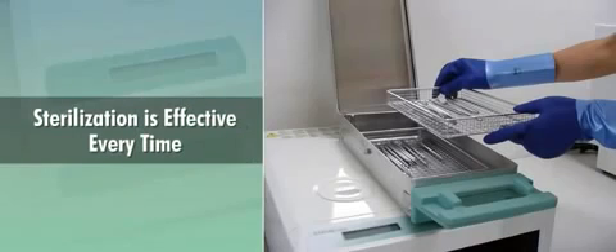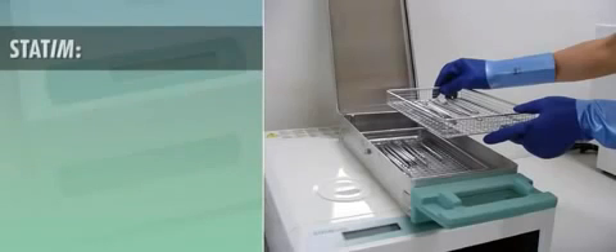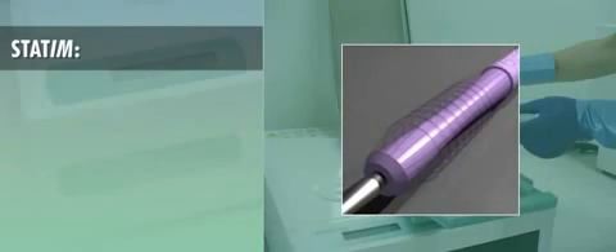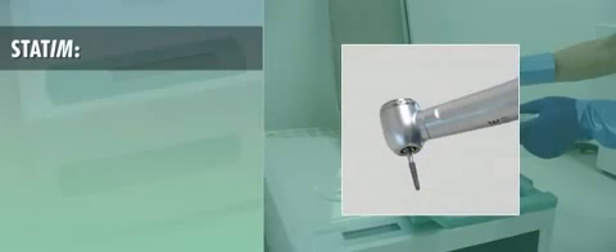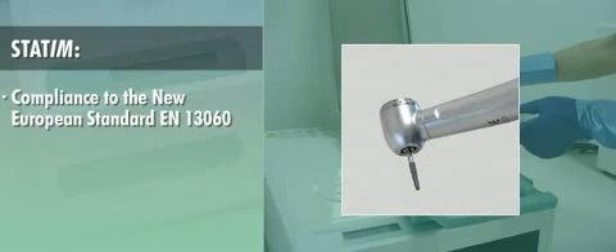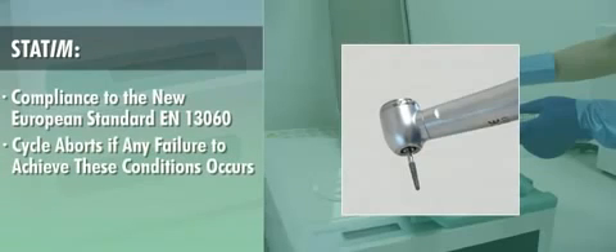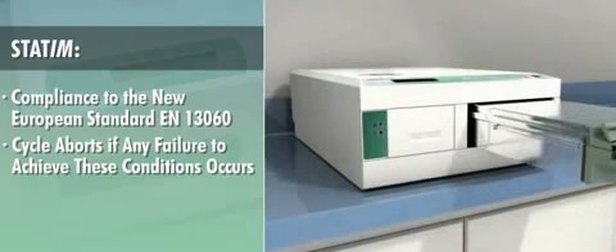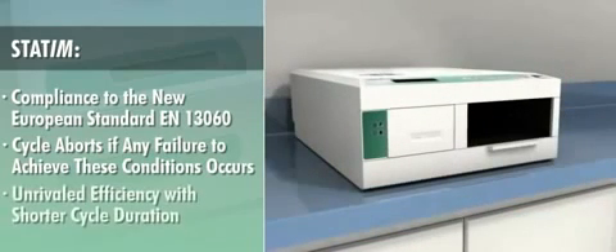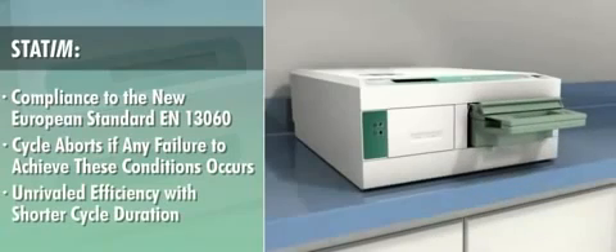Don't let STATIM's quick sterilization time fool you. Sterilization is effective every time, purging all of the air from the fine lumen of dental handpieces. STATIM's biological and physical effectiveness has been proven in tests on a wide variety of dental handpieces, which validate compliance to the new European standard EN 13060 for small steam sterilizers. As an extra measure of reassurance, STATIM cassette autoclaves have a process evaluation system which is designed to monitor sterilization conditions and to abort the cycle if any failure to achieve these conditions occurs. Independent tests show that STATIM delivers dramatic improvements in process efficiency with shorter cycle duration as compared to larger volume autoclaves.